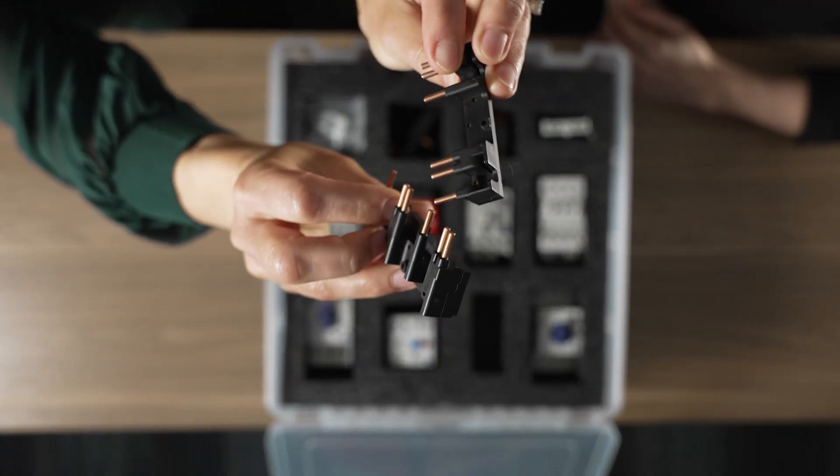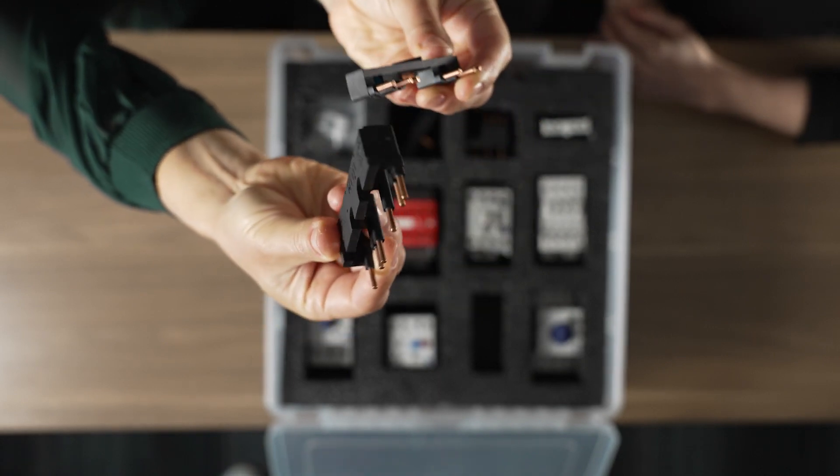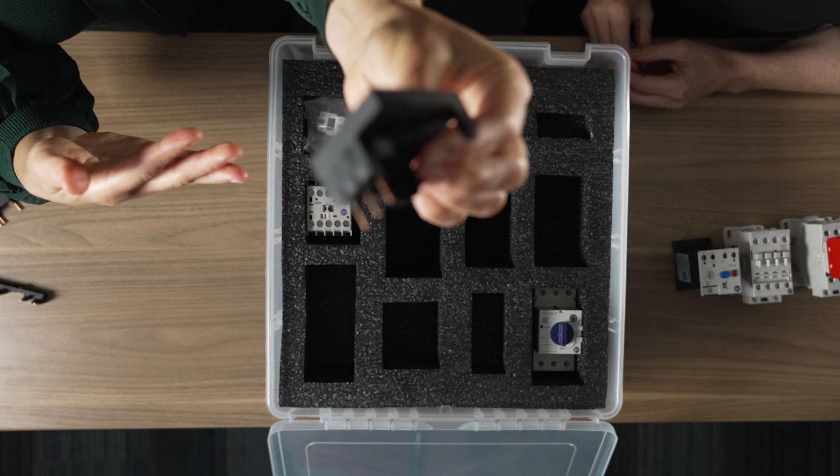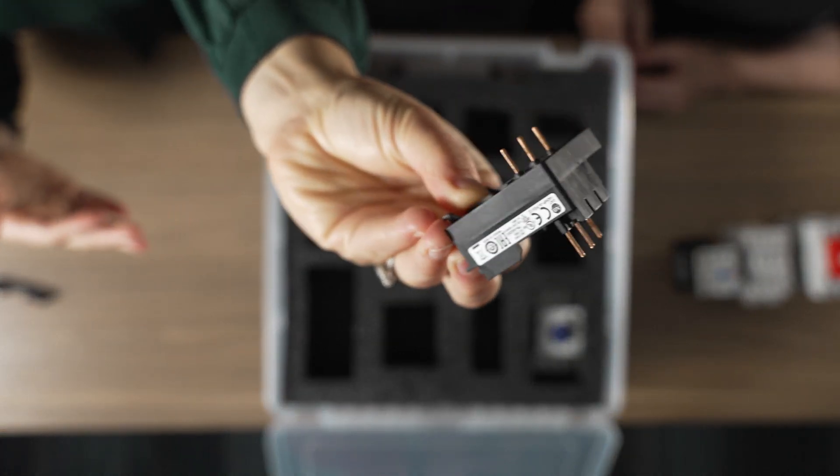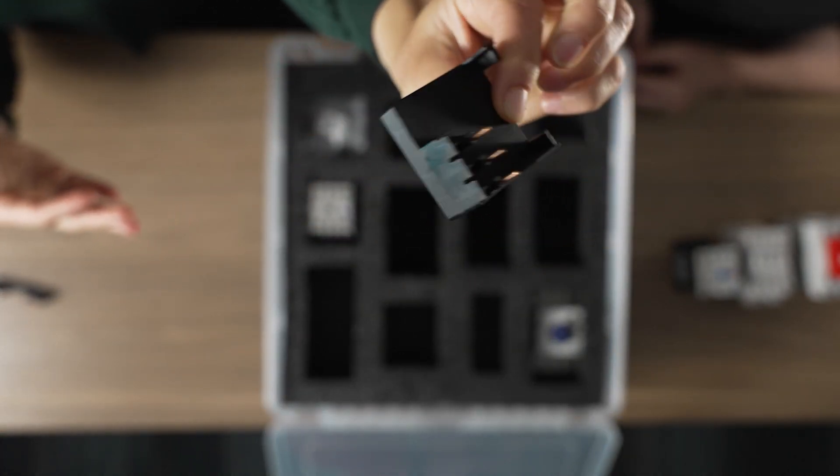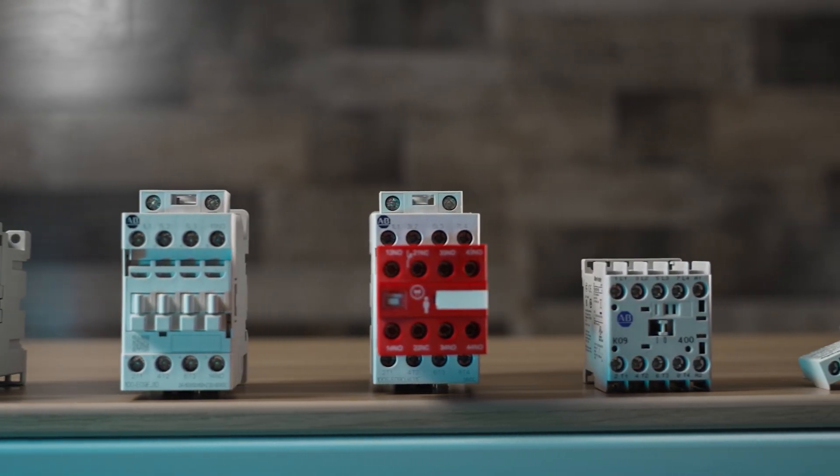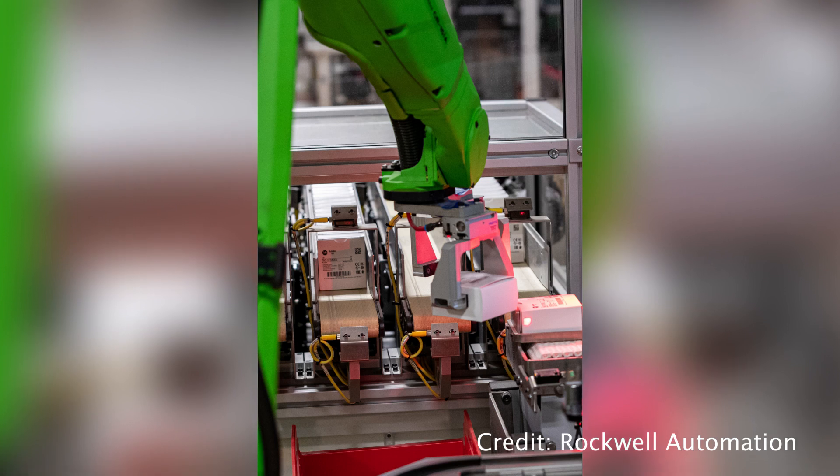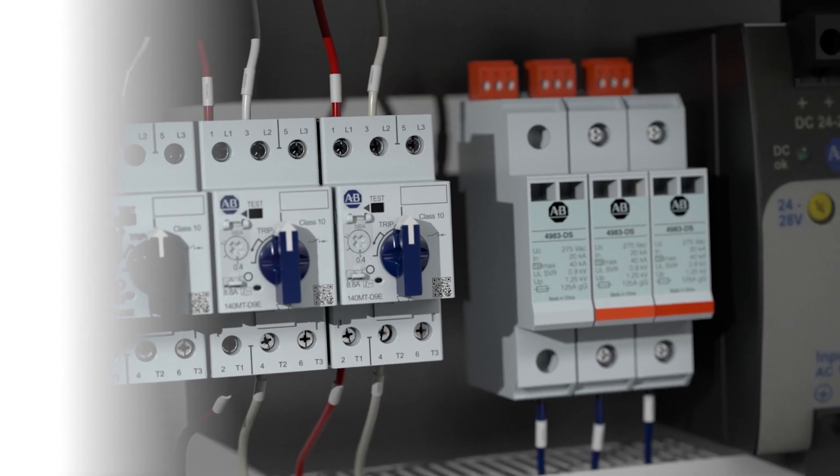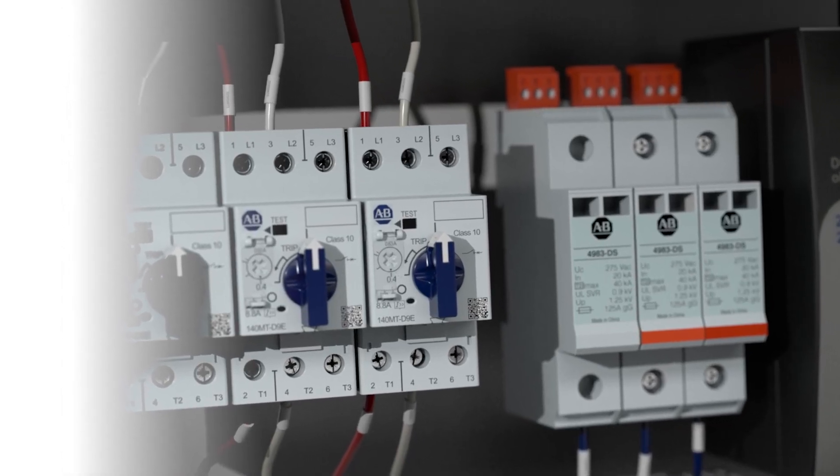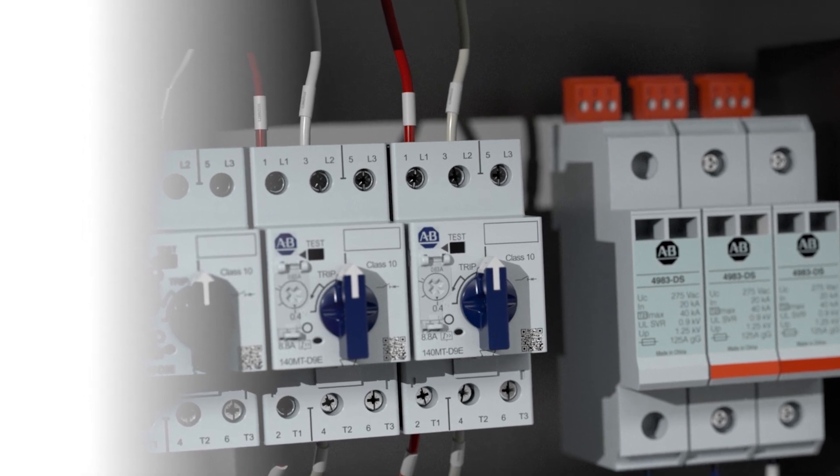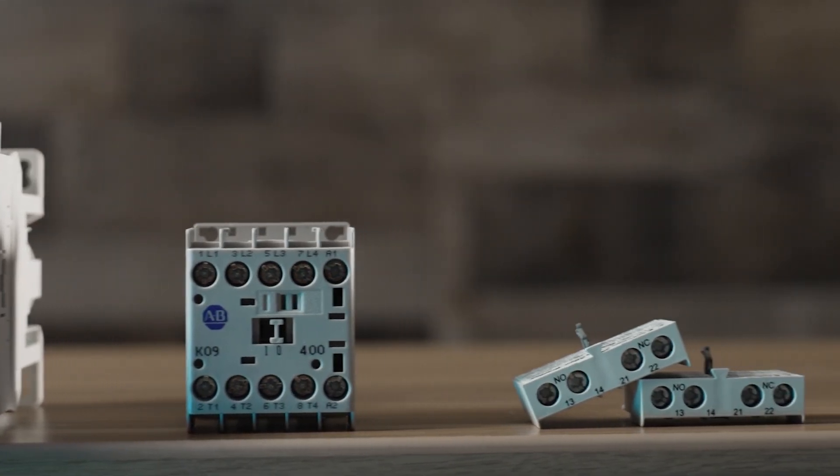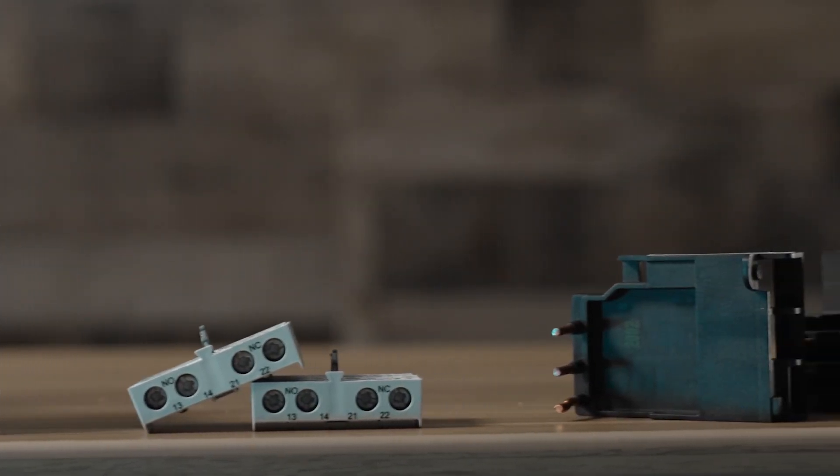There are also reversing bus contactor kits. These connect motors that must run clockwise and counter-clockwise while ensuring the motors are protected against overloads. These and other connecting modules from Rockwell greatly simplify machine installations, especially where a dozen, two dozen or even more motors run a production line. That's because these modules save installers from having to cut and label huge wire arrays. All connecting modules are tested and certified for listed short circuit protections and current ratings, satisfying both safety and regulatory requirements.